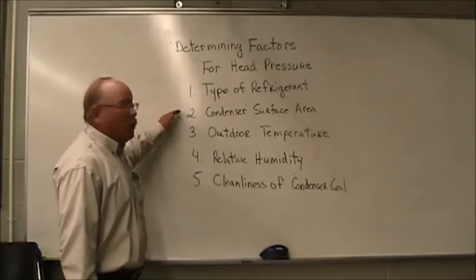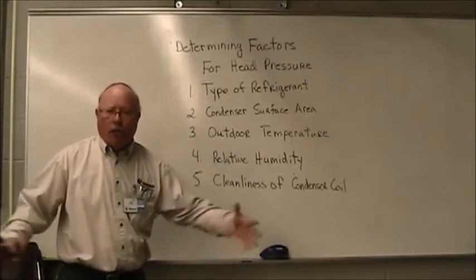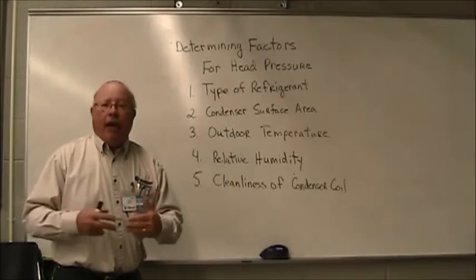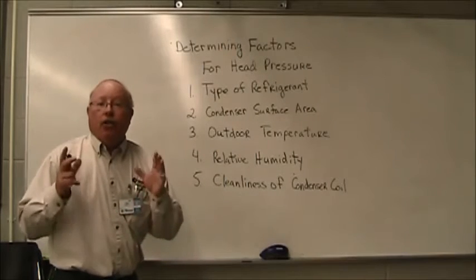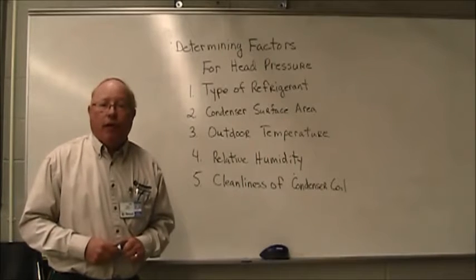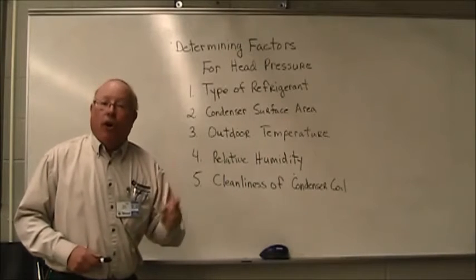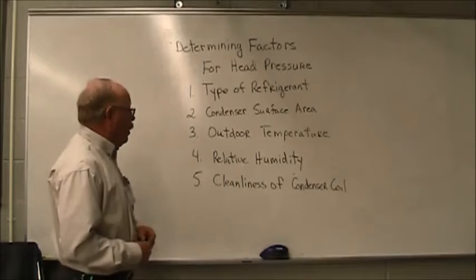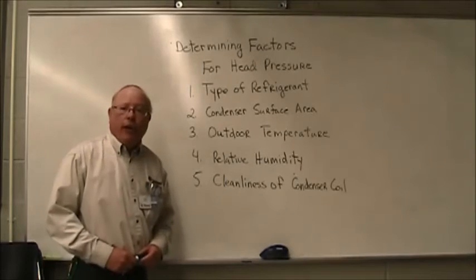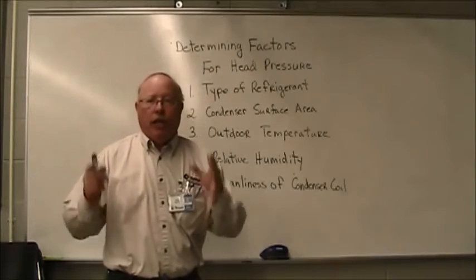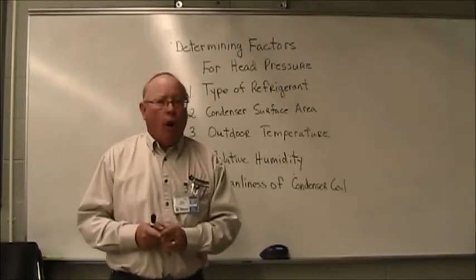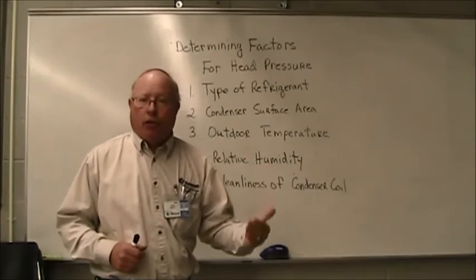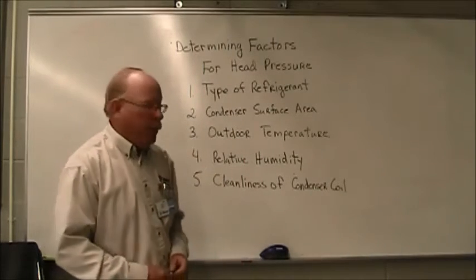The condenser surface area — how large or small is the condenser? The vessel itself and the surface area that it has to allow heat to be dissipated from the condenser is going to determine what your head pressure is going to be. What is the outdoor temperature? If the outdoor temperature is warm, the head pressure is going to be higher. If the outdoor temperature is cooler, then the head pressure is going to be lower.